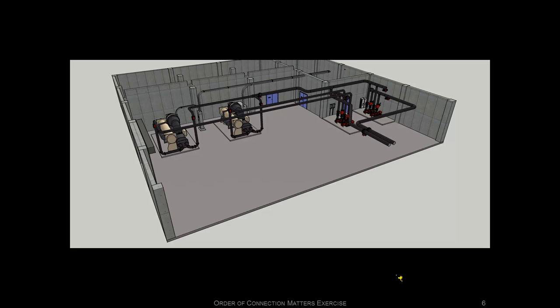Obviously the model is still in stages of development. For instance, there's no condenser water system there, and if you go in the switchgear room, there's no switchgear there, and the pipe's not insulated, and there's no pipe hangers and stuff like that. But there's actually enough information here for you to draw a system diagram, and in fact it's a little easier because there is no insulation there and 20 other systems overlaid on top of it.